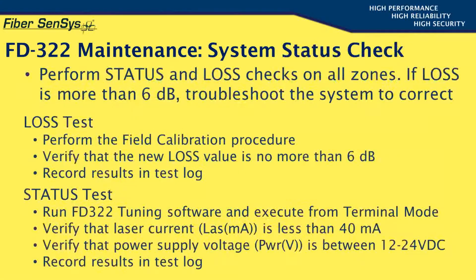We recommend that a system status check be made every 180 days, although it's certainly okay to perform it along with the visual and performance checks every 90 days. The status check involves performing status and loss checks on all zones. In order to guarantee reliable performance, every zone should have a loss less than or equal to 6 dB. If any zone has higher loss, troubleshoot the system to correct the situation. To measure the zone loss, perform the field calibration procedure as described in an earlier video segment. Verify that the new loss value is no more than 6 dB and record the result in the test logbook.